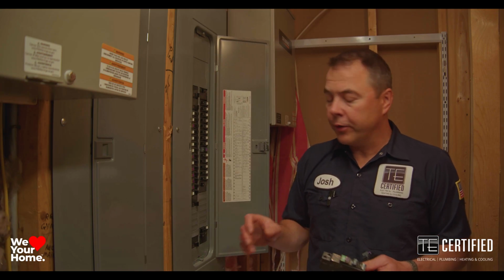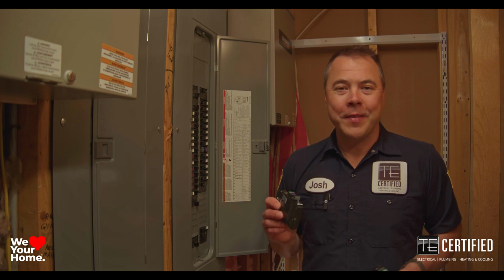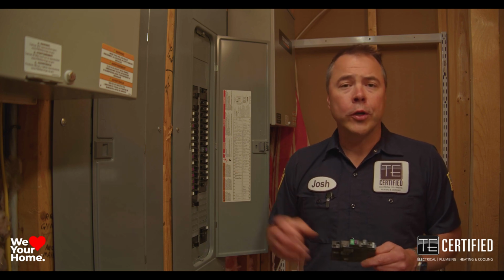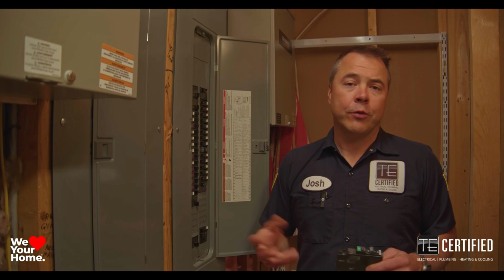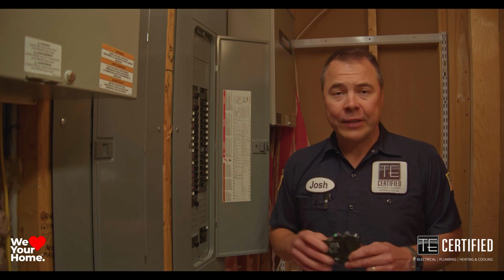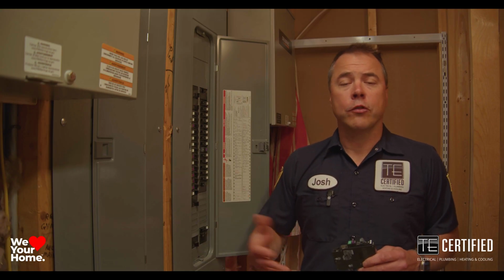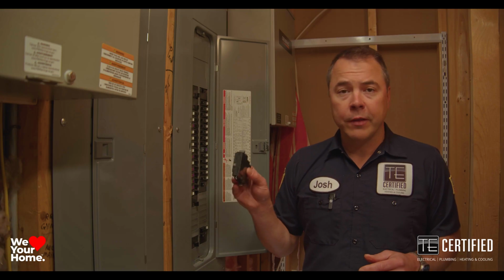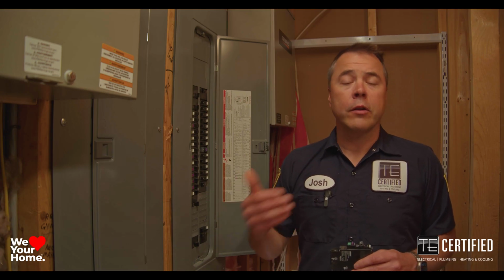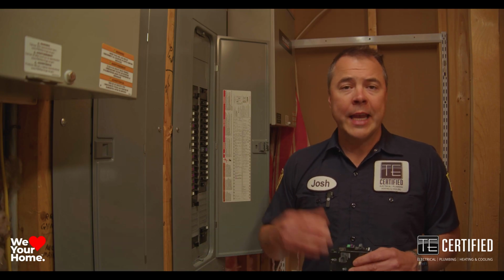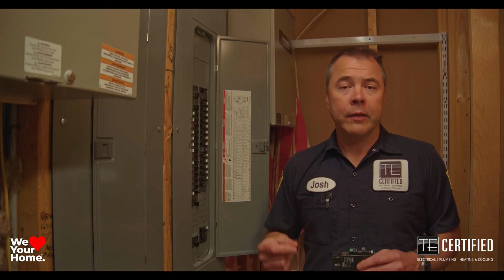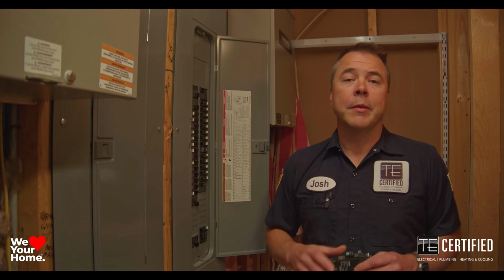Old-fashioned breakers were a lot smaller than this, and all they have is a thermal overload. So if the circuit gets hot, it trips. Arc fault breakers actually detect arcs inside your circuit. There's a computer chip inside of this breaker, and it monitors your circuit 24 hours, and if it detects an arc, it will immediately turn the breaker off. This has been a game changer.